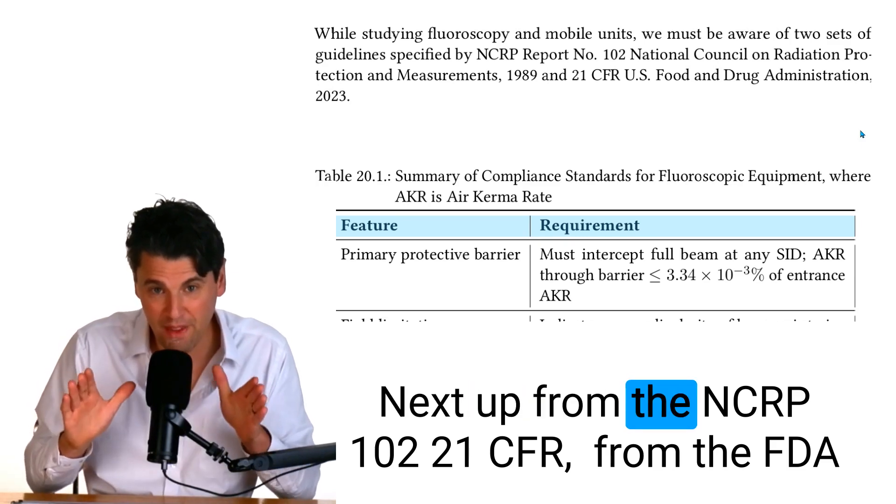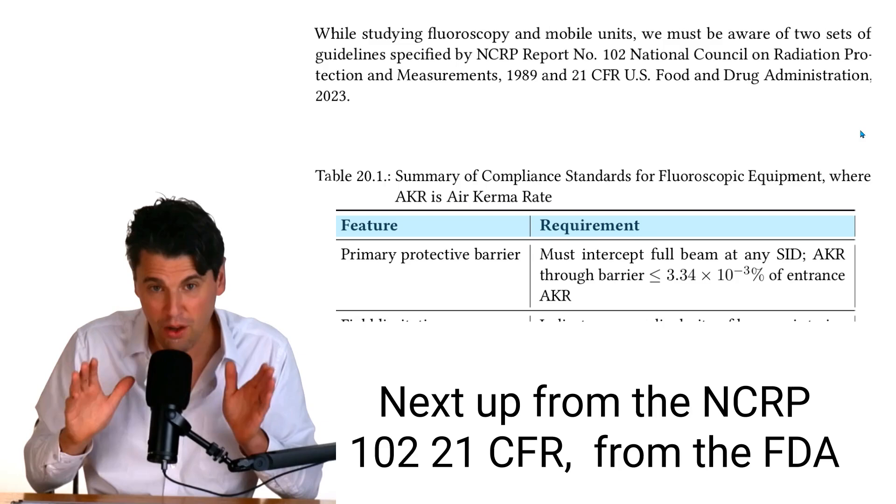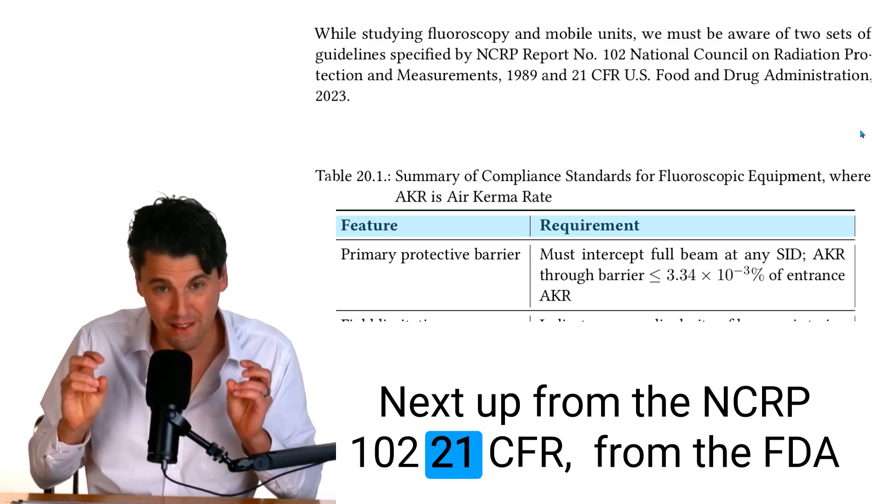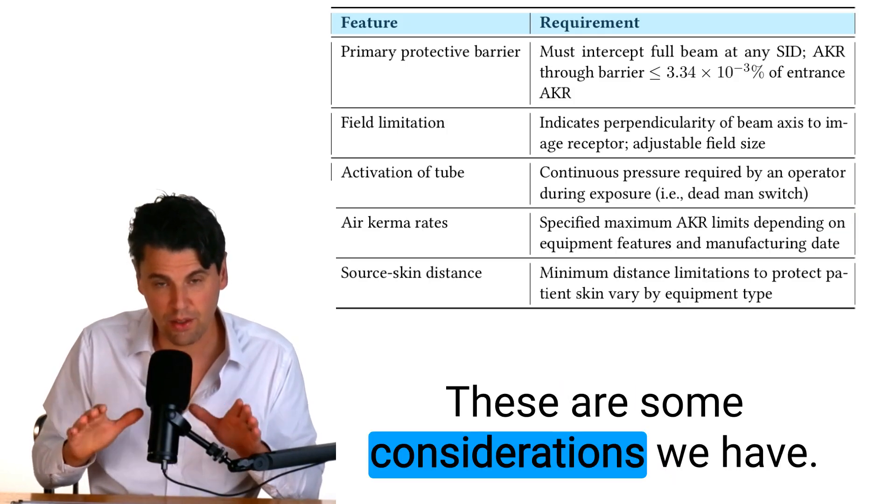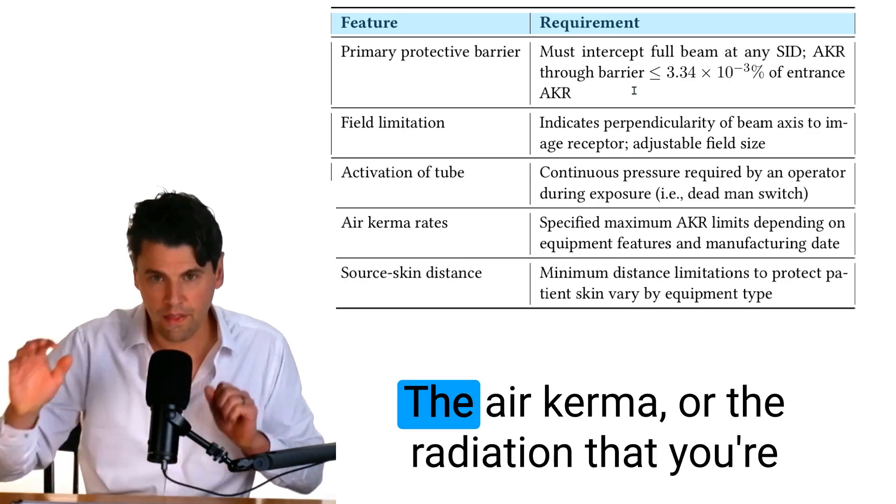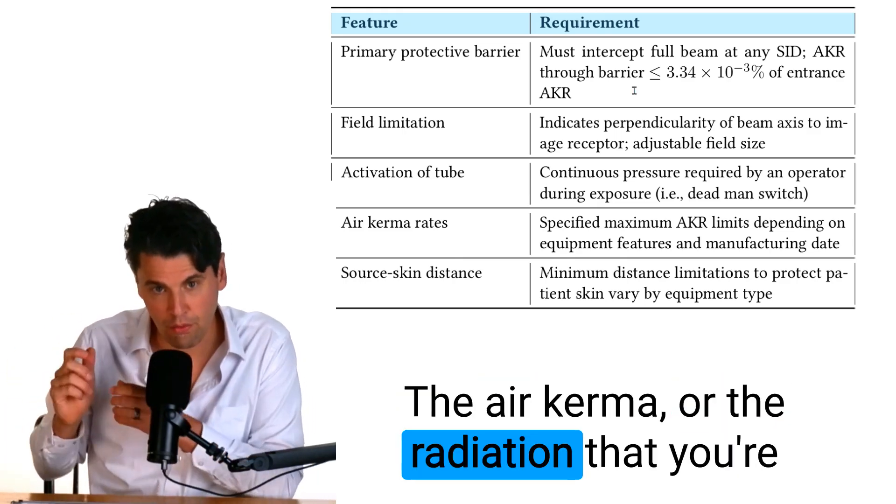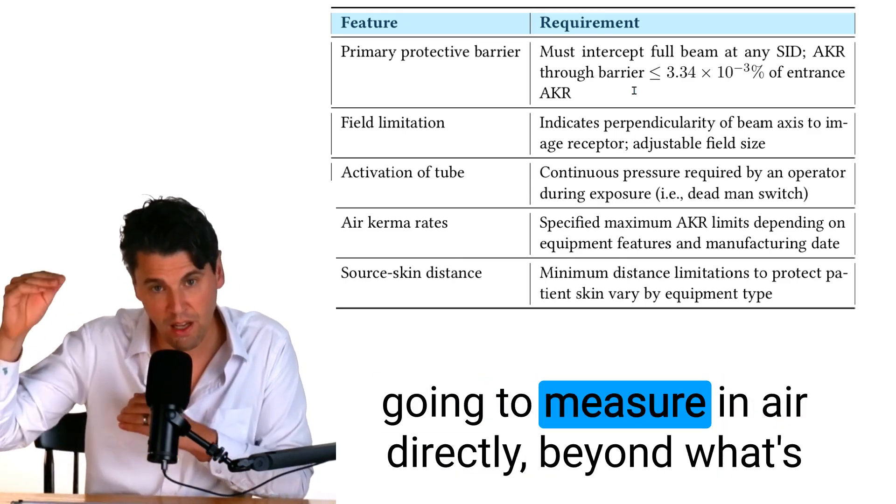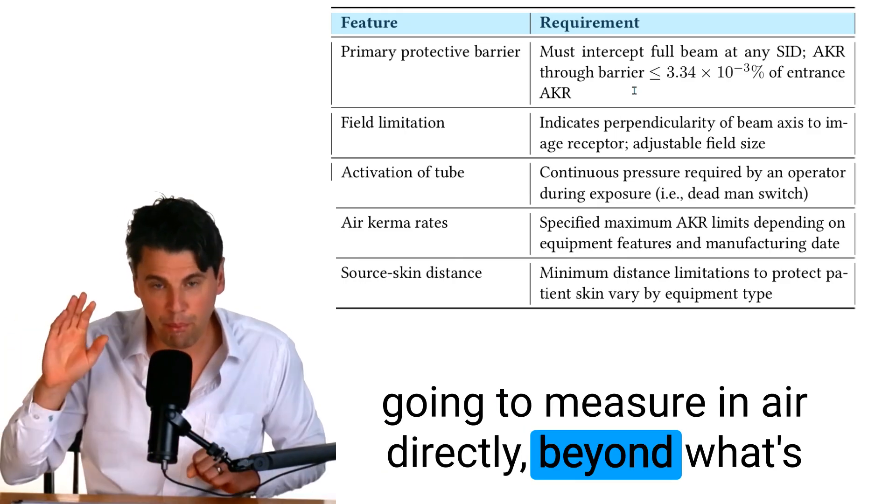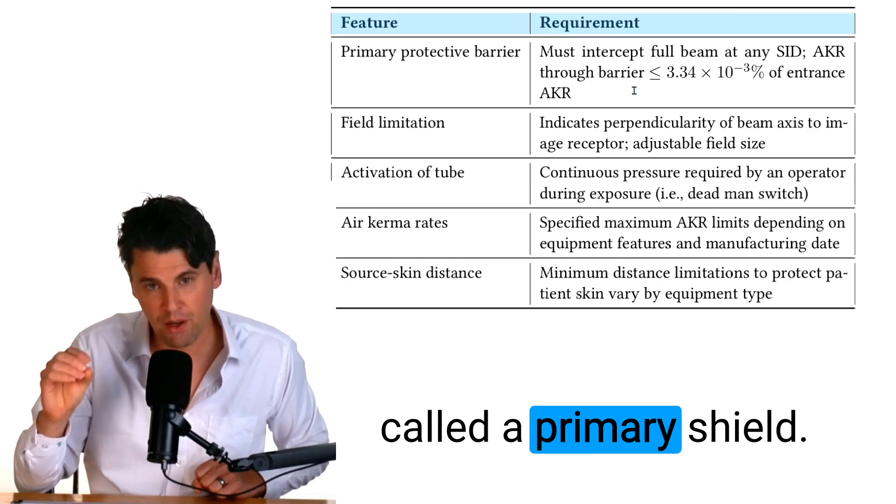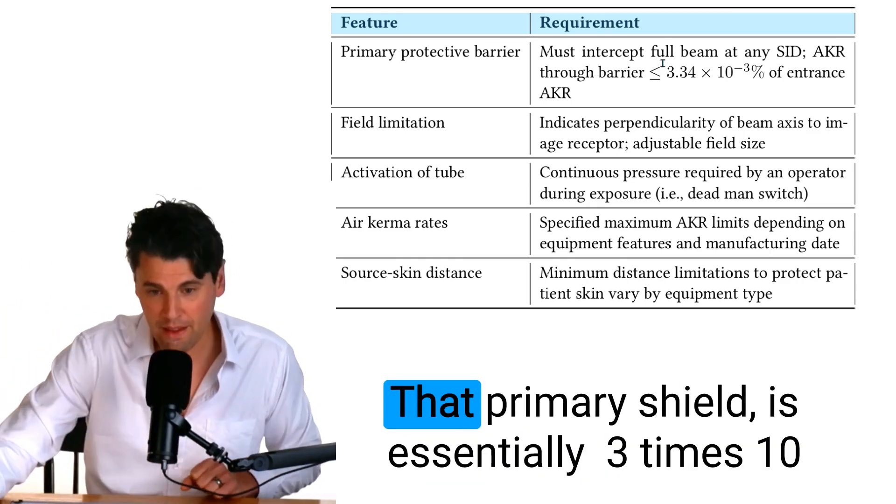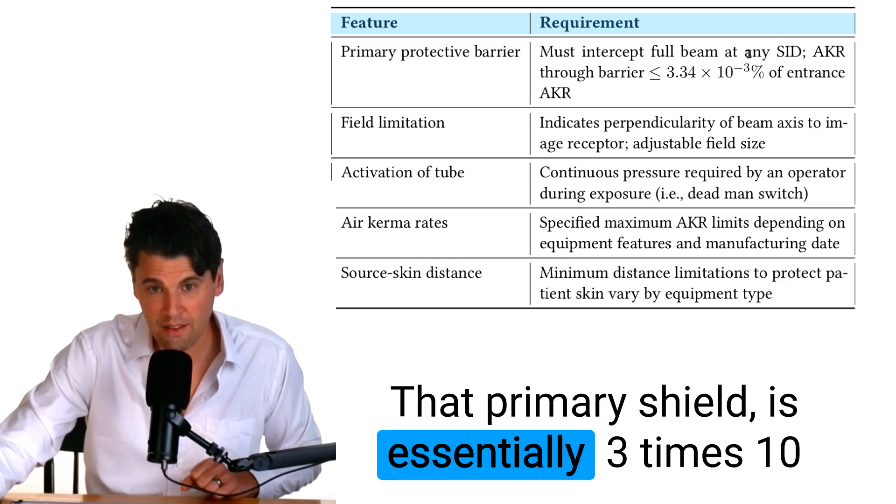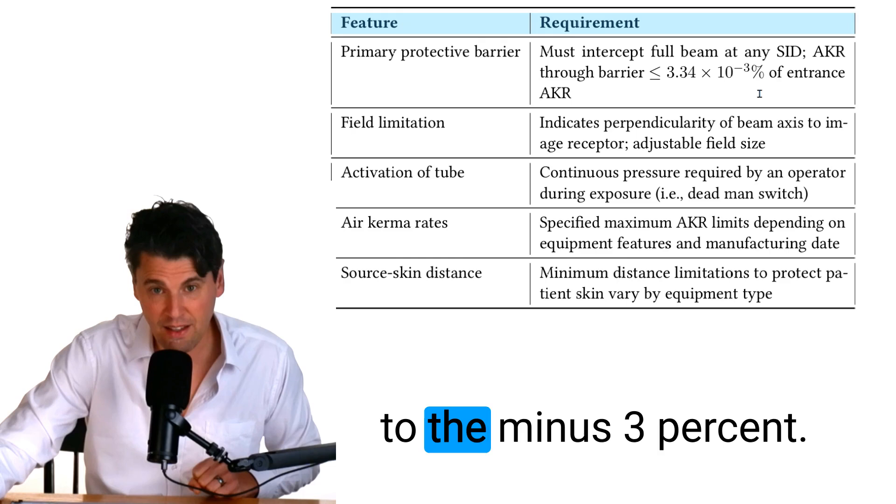Next up from the NCRP 102, 21 CFR from the FDA for fluoroscopy and mobile units, these are some considerations we have. The air kerma or the radiation that you're going to measure in the air directly beyond what's called a primary shield, this means a leaded wall for instance, that primary shield is essentially 3×10^-3 percent.